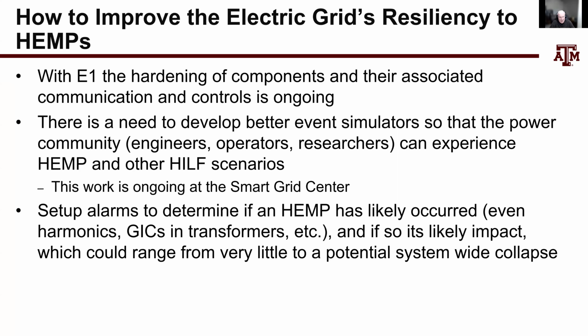I think if power engineers see this, they might come up with effective mitigations. You could set up alarms to determine if a HEMP has likely occurred, and those alarms could trigger potential remedial action schemes. In the West, they have a remedial action scheme that separates North and South. We might want to consider that in other grids as well to prevent a cascading collapse.